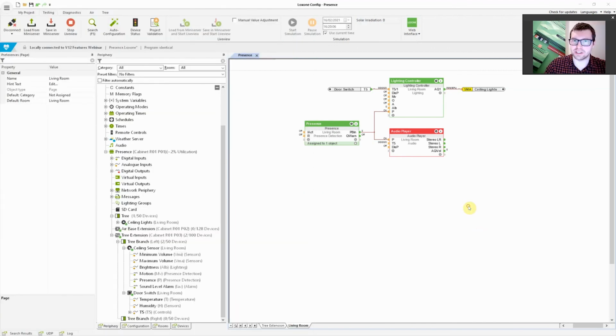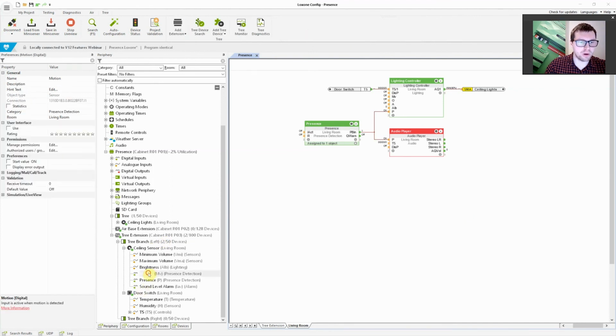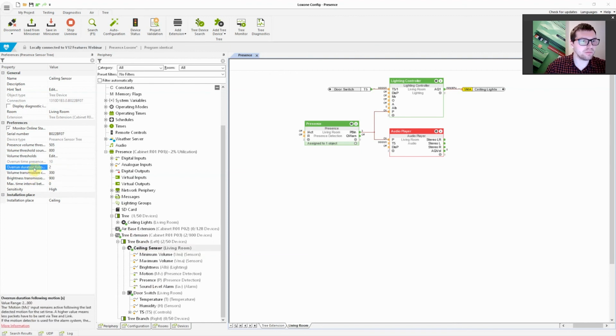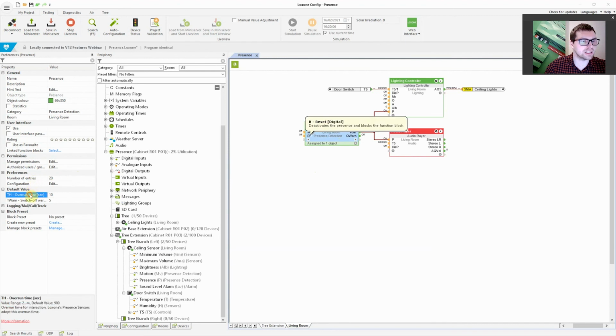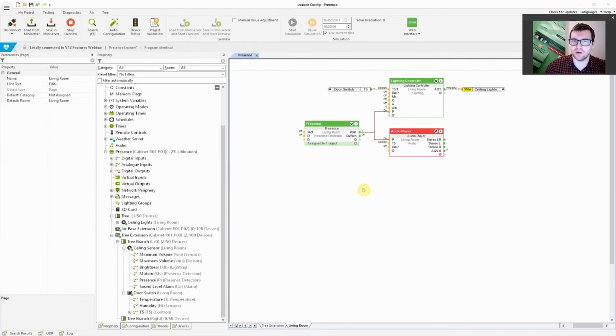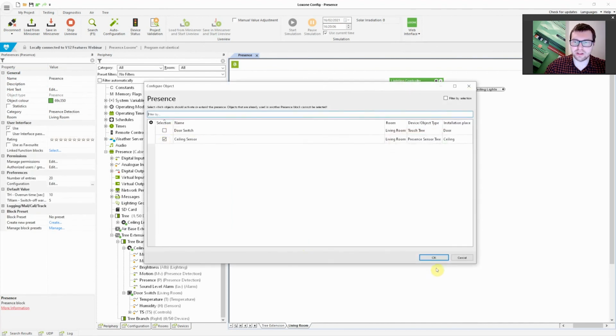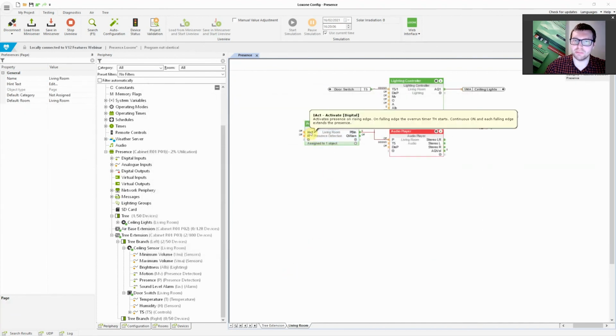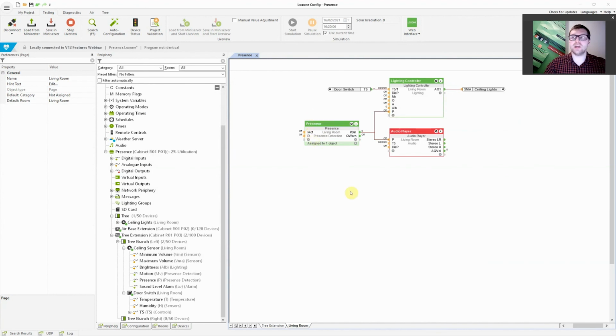And then we have the presence sensor. So again, a quick go over. Motion and acoustic equals presence. Motion on its own triggers both, but sound on its own triggers nothing. You always have to have motion first before sound. The sensor has several overrides built in, as well as several volume thresholds. The overrun time for presence doesn't need to be changed, however, because it will take that from the presence sensor block itself. As many sensors as you like can be assigned within this block, and any additional sensors can be added to it.